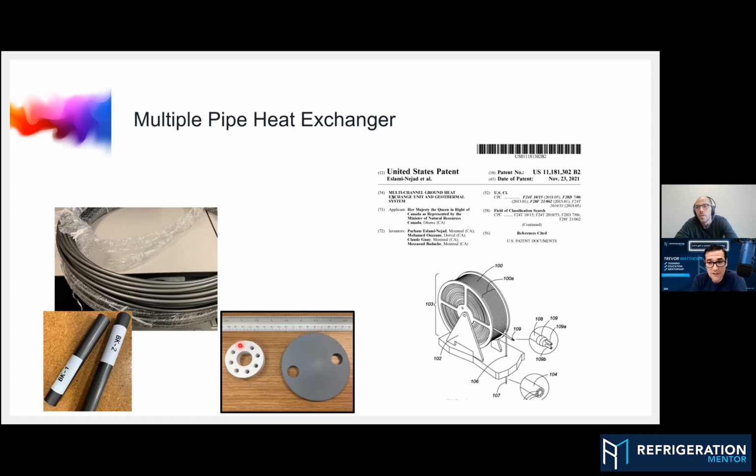Because I'm curious. Yeah, the thing is, after drilling the hole, you drill a bit bigger than the 2-inch so that you can insert that, and eventually, probably from the middle part you see here, you can inject some grout inside to get the perfect thermal contact.